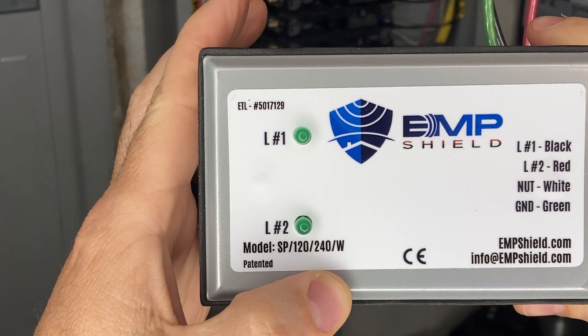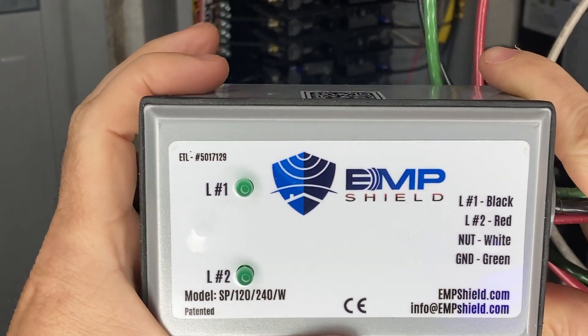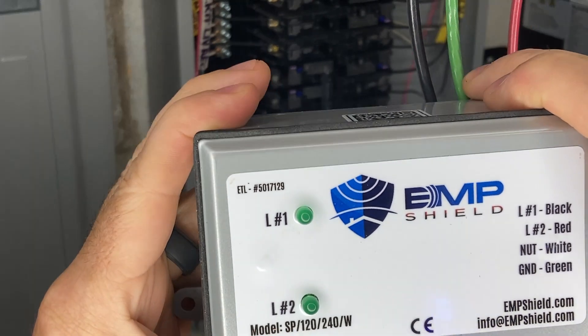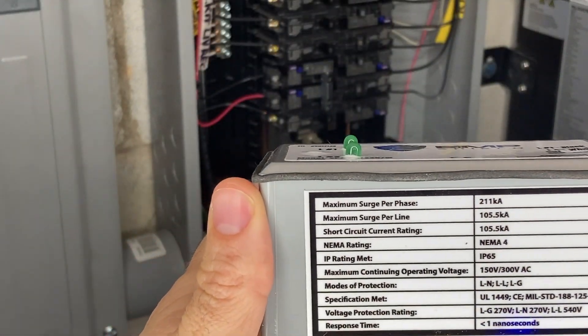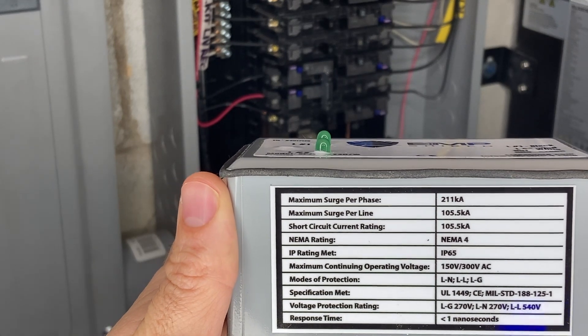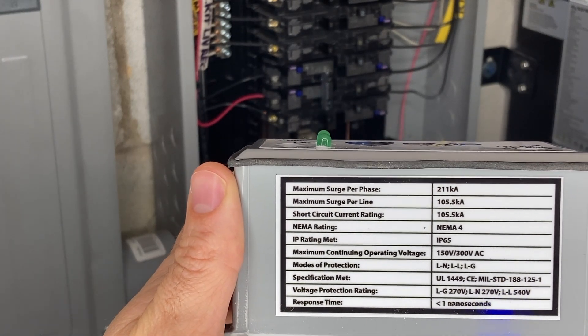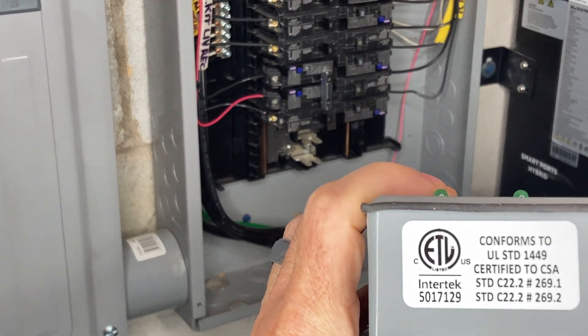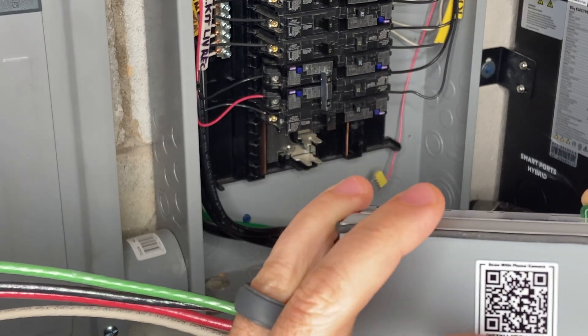This is the EMP shield meant for your AC side of things. It is rated for 120/240 volt. It's got a line one, line two, neutral, and ground. It's going to have green illuminated lights once it's installed, just showing that everything's good. It has a maximum surge per phase of 211,000 amps. NEMA 4 rated, IP65 rating. Conforms to UL STD 1449. Intertek rated. And there's a nice QR code for installation help.